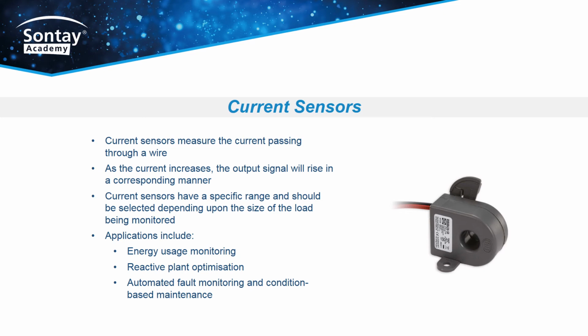Current sensing offers a number of benefits. Current sensors can be used to monitor the status of pump and fan motors where it is not possible to use a differential pressure sensor. This includes retrofit applications where drain down is prohibitively expensive, and for HWS return pumps where the control of Legionella precludes the use of differential pressure monitoring.